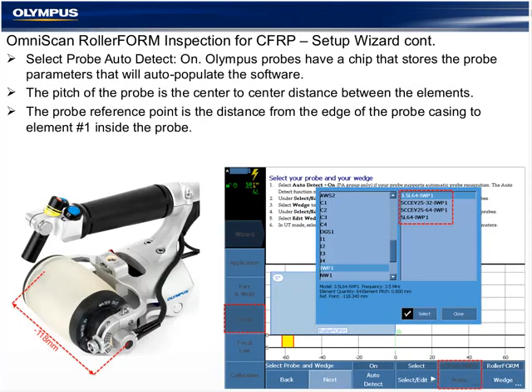Continuing on in the wizard, we will see the auto detect on. All Olympus phased array probes contain a chip that contains the essential variables for the calculator, to include the model, the frequency, the number of elements, and in this case we're going to be using a 3.5 megahertz 64 element probe that has a center-to-center element size, also called pitch, of 0.8 millimeters. The reference point in the probe is the measurement from the edge of the casing to element number 1 inside the wheel.